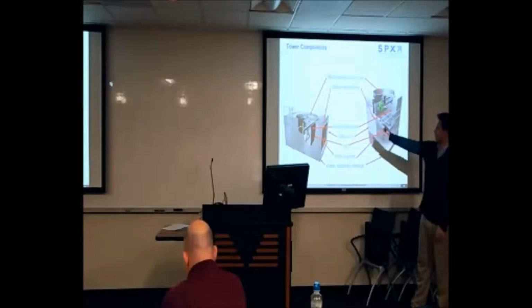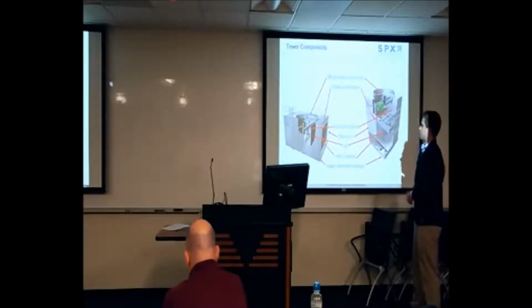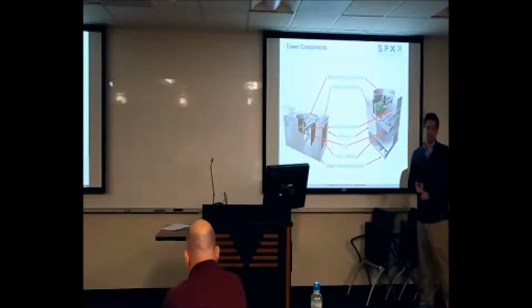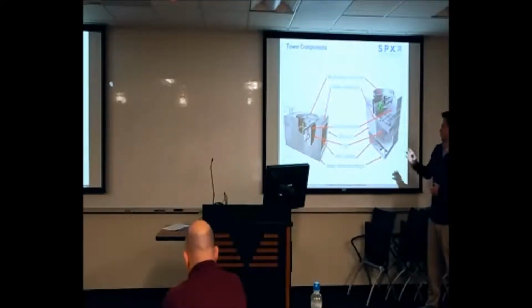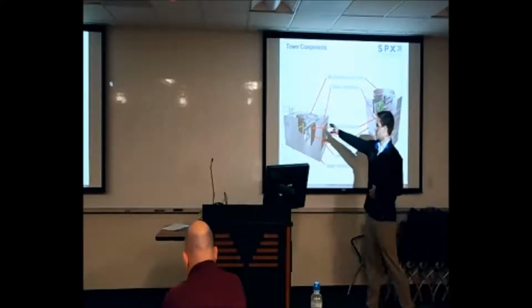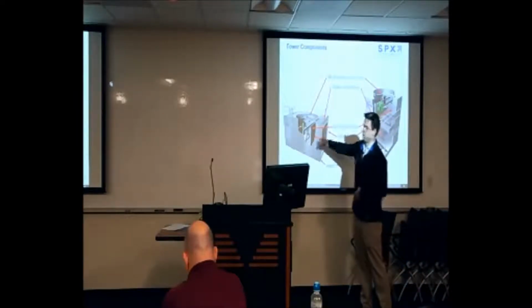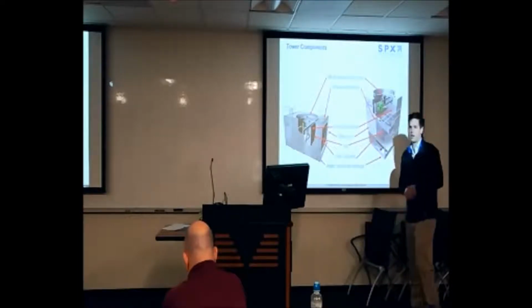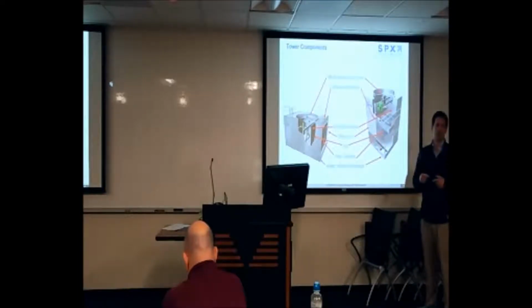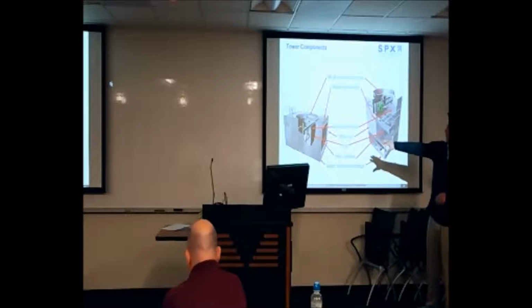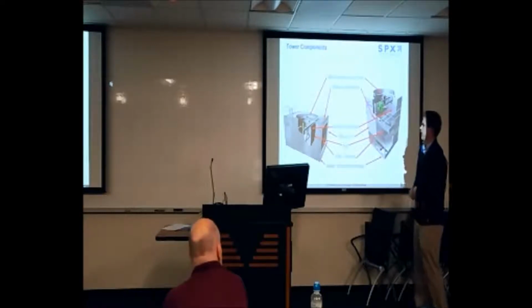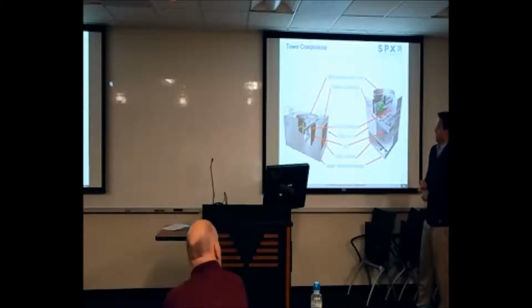So within the crossflow tower, we'll run through these components here. First off, you have mechanical equipment. So your mechanical equipment is what's going to be drawing the air. This is an induced draft fan, which means there's an axial. You actually have fan blades that are drawing air through and up out of the tower. A forced draft fan, which some of you may or may not be familiar with, has a centrifugal blower that's actually pushing air up and out of the tower. Your tower is a axial induced draft fan, just like it's pictured here on the left. With your mechanical, you have your fan, you have a gear reducer, and you have your motor. Those are your three main mechanical components, and you'll be doing maintenance on all three of those.